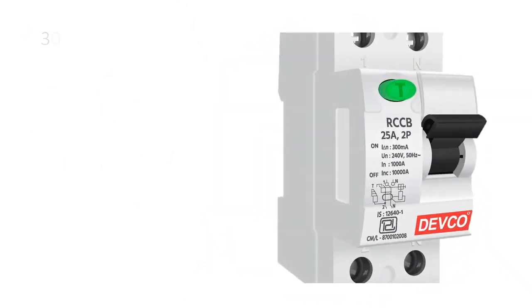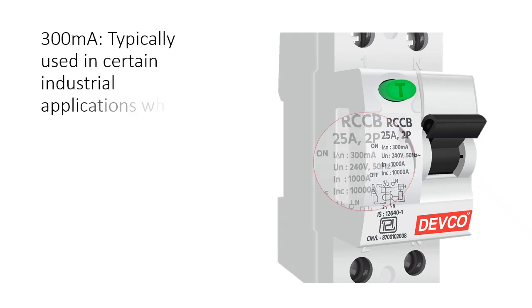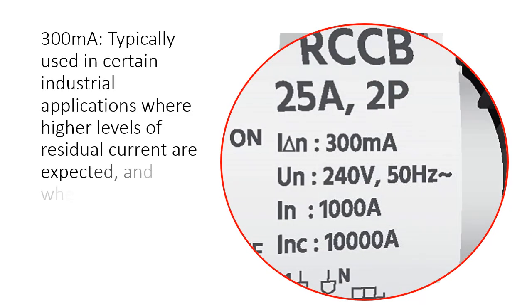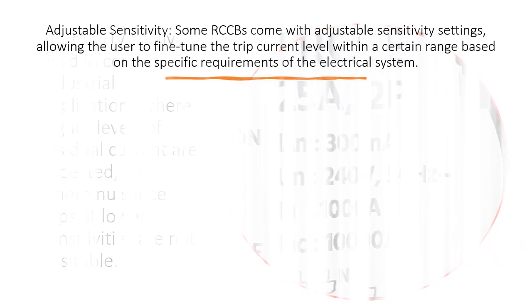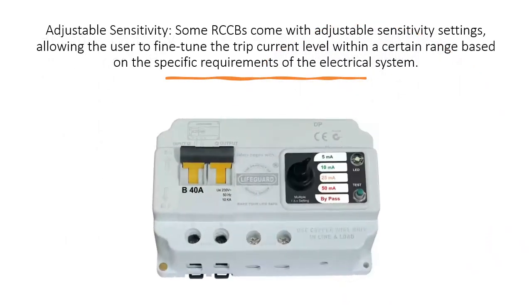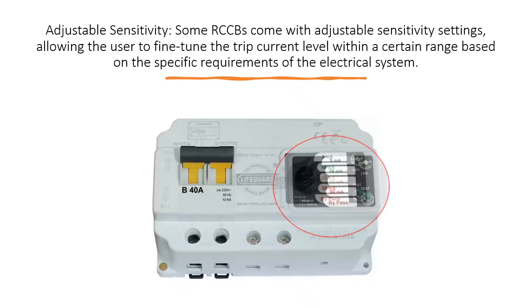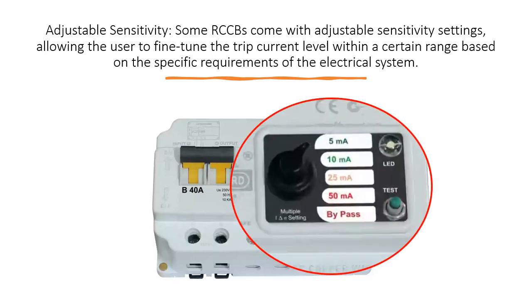300mA is typically used in certain industrial applications where higher levels of residual current are expected, and where nuisance trips at lower sensitivities are not desirable. Some RCCBs also come with adjustable sensitivity settings, allowing the user to fine-tune the trip current level within a certain range based on the specific requirements of the electrical system.